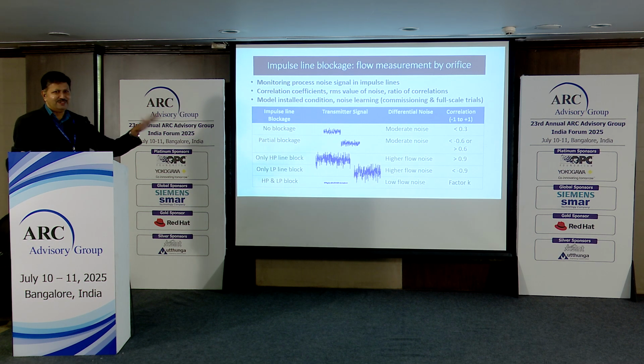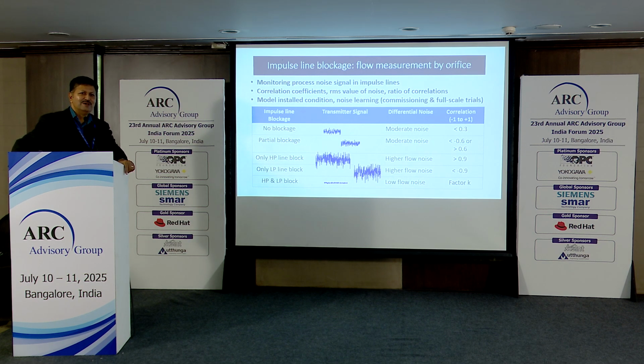Right? So on our end, of course that is not connected with Honeywell, we had just tried to assess and come out with some parametric evaluation. We found that yes, it is possible, having some correlation from the noise based on the RMS value of the signals from both the positive and the negative limb, you are able to determine that one of the limbs is choked or both the limbs are choked. Of course for the partial blockage, the figures you see are with maybe something like 96% choked. It is literally going undetected till about 90% is blockaged, right? So that is what we could actually see.